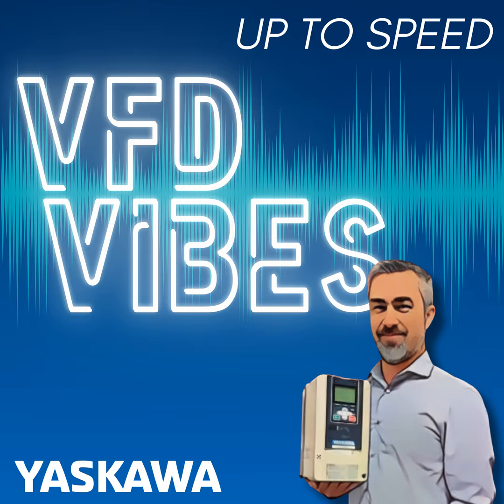You don't want to say, well, okay, I'm going to run this drive at 50 degrees C ambient out in the sun. And you say, well, yeah, but if you're going to do that, don't have a horrible amount of line imbalance to put stress on the input rectifiers and the bus capacitors. So if you're going to run at a high temperature, maybe you want to put that line reactor in there. So there are things like that. If you don't do everything all at once, you can usually extend the life.